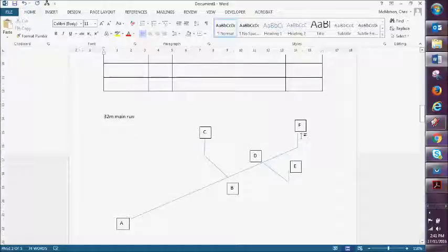Does that mean you'd go on to this table, look at 32, you'd go straight up to 35? Yes. Again, you can never undersize. Never undersize. Same gas, same pressure, same everything else, so you can stay on that table.